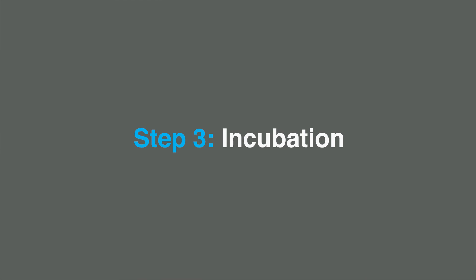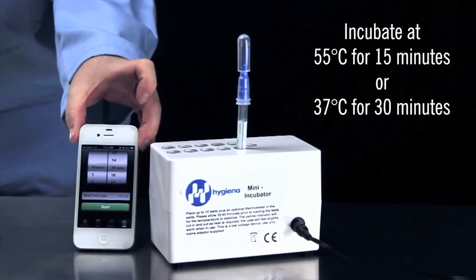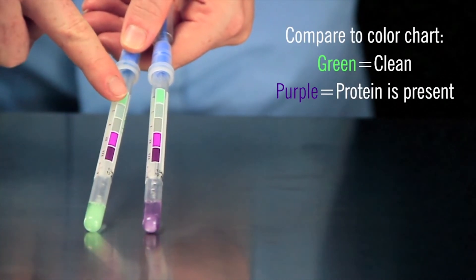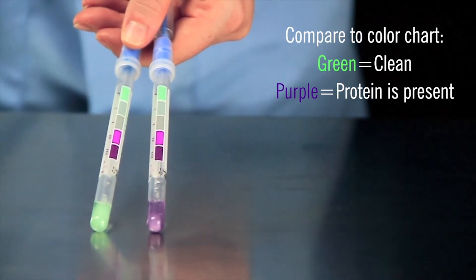Step three: incubation. Incubate the device for 15 minutes at 55 degrees Celsius or 30 minutes at 37 degrees Celsius using a dry incubation block. When the time is complete, compare the colour of the liquid against the colour chart on the AllerSnap label. Green means clean and purple means protein was detected.